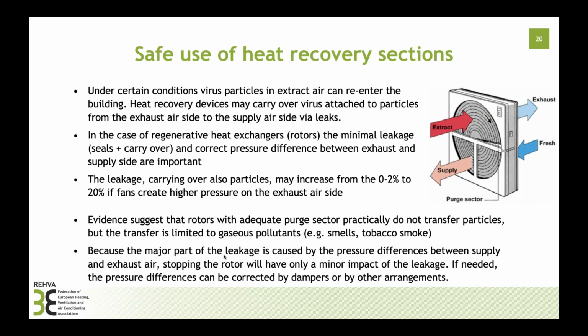What applies for ventilation system hygiene, what is indeed important in all conditions, but especially important in epidemic conditions, are leakages in the ventilation system, so that extract air, return air can leak to the supply air side and then pollute this supply air. And if there are significant leakages, then you can expect significant virus concentrations also.